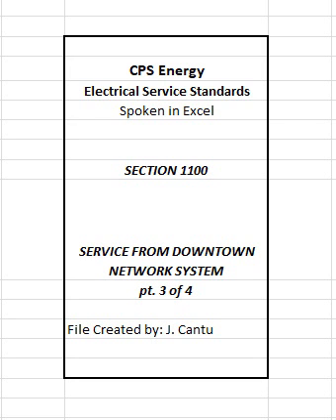4. Customer shall furnish all conductors and CPS Energy approved connectors and copper flags, if required, on load side of fuse pads. Service entrance shall be copper bus or copper conductors. Where service entrance conductors are installed, customer shall furnish single barrel, 2-hole tongue lugs. Mounting holes in tongue shall be 9/16 inches and spaced vertically and horizontally 1 3/4 inches center to center. Cable lug width shall not exceed 1 3/4 inches and height shall not exceed 2 1/4 inches.